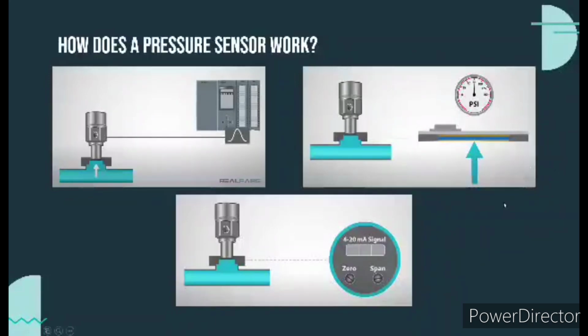Pressure sensors need to be calibrated so it knows what voltage or milliamp signal corresponds to what pressure. This is a basic zero and span calibration, or minimum and maximum, which is a common job for maintenance personnel.